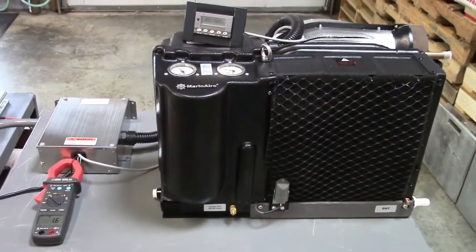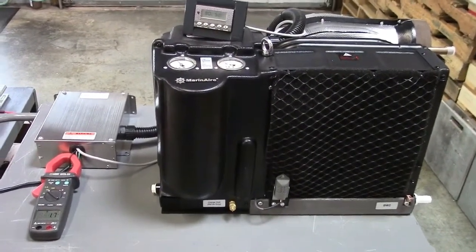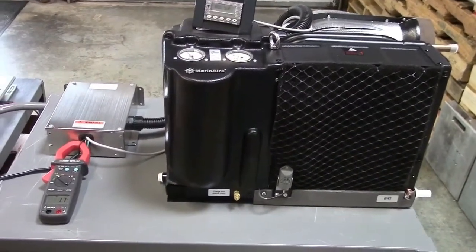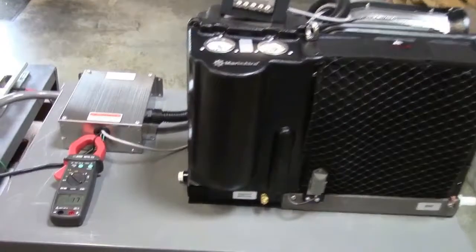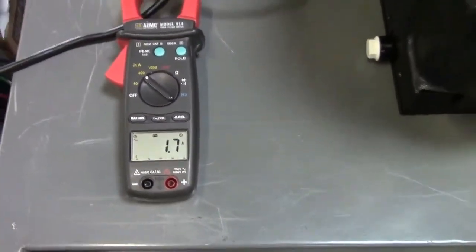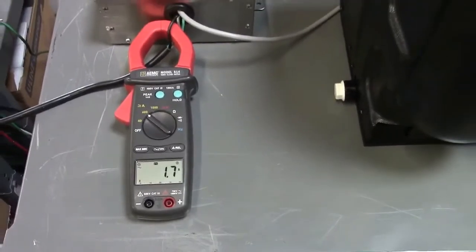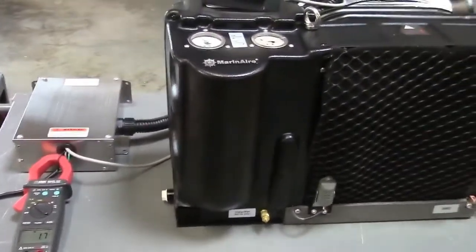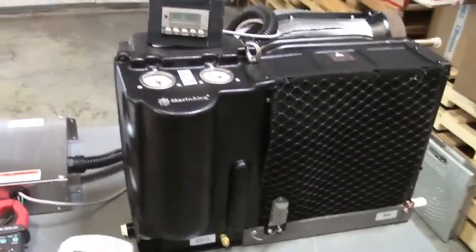We're going to start up our MarinAire 16,000 BTU unit and see what the peak current is when the compressor starts. We've got a peak reading ammeter here which measures within one millisecond, so within a thousandth of a second. We have no pump connected, but the fan will be running.